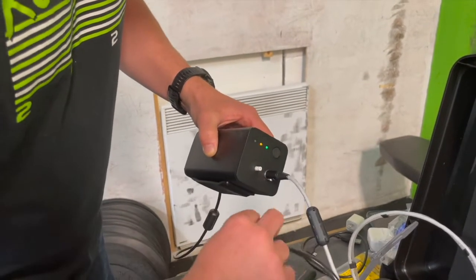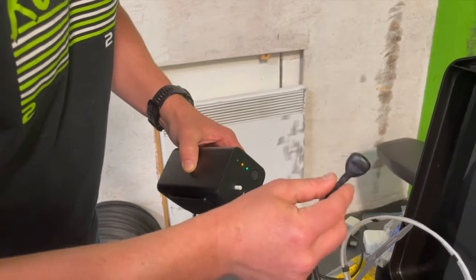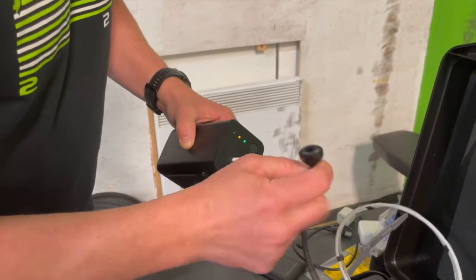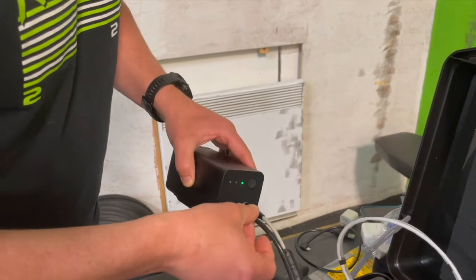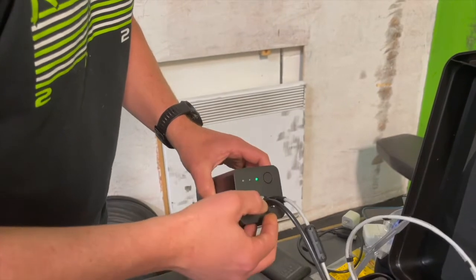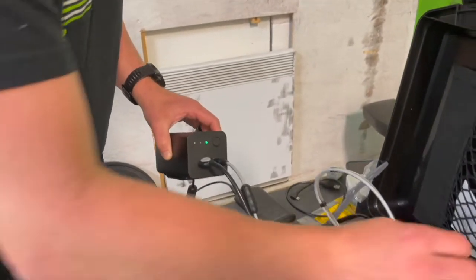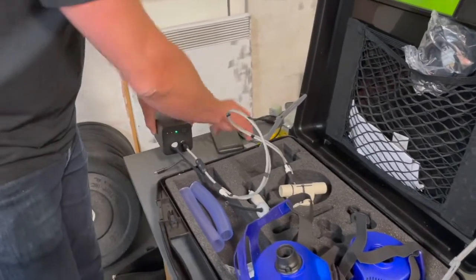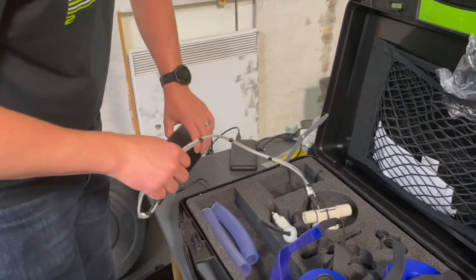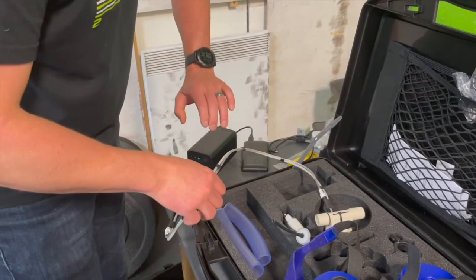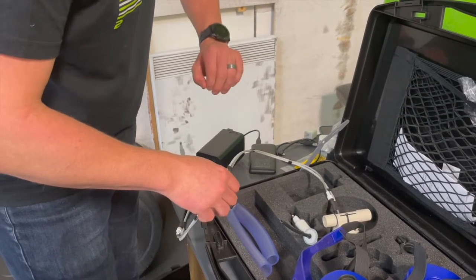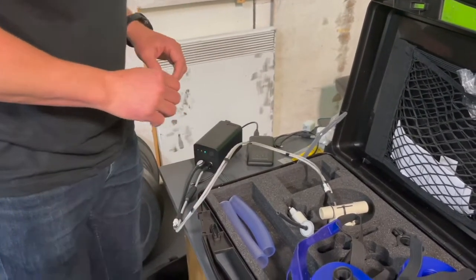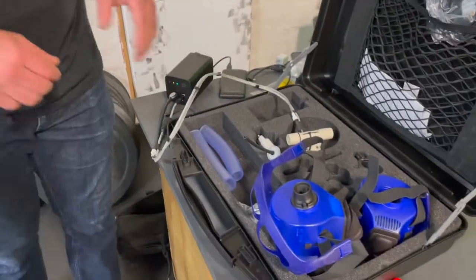And then the other part is the flow sensor has a little hole on the end, and that's going to go onto this white post and click. Okay, so our flow sensor is set up. We're attached to battery power here. That unit has almost been charging now for just over 3 hours at this point, so we should be getting ready to go soon. We're going to let this guy sit for about 10 minutes.